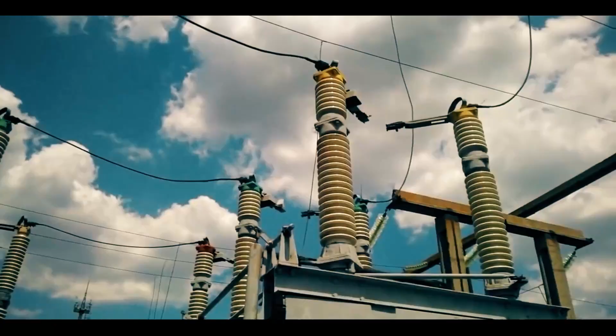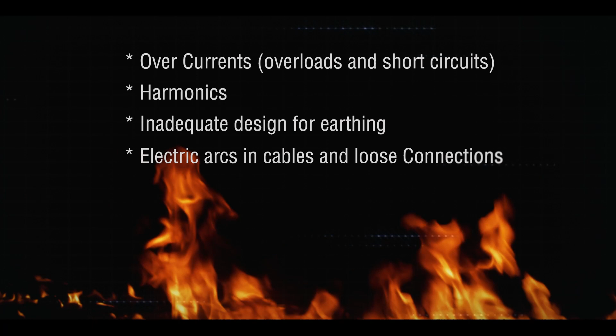Fire in electrical installations may be broadly caused by overcurrents, harmonics, inadequate design for earthing, electric arcs in cables and loose connections, failure of protection devices or wrong selection of protection devices, wrong selection of cables or wires, use of outlived or damaged equipment, over voltage, and improper or no verification and testing of installations.